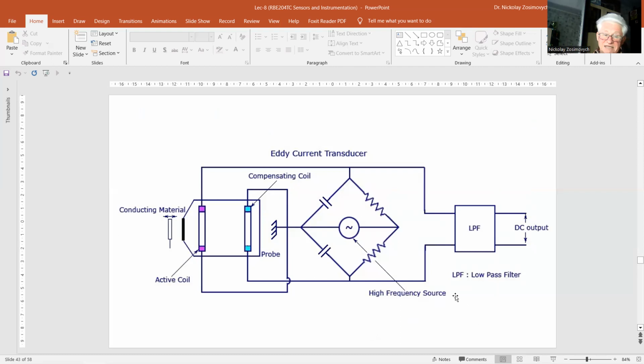The presence of capacitance and the skin effect make the impedance of an eddy current sensor frequency dependent. So the transfer characteristic contains information about not only the distance between the sensor and the target, like the lift-off, but also the properties of the target: thickness and material. In general, the sensor can be modeled as a second-order system, of which the resonance frequency and the quality factor or damping are determined by the material properties, the thickness, and the lift-off.